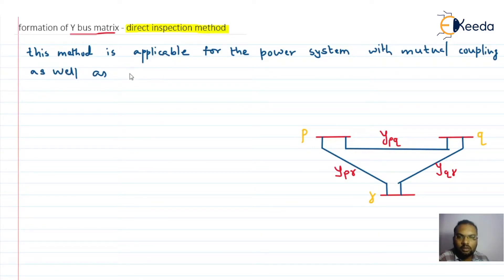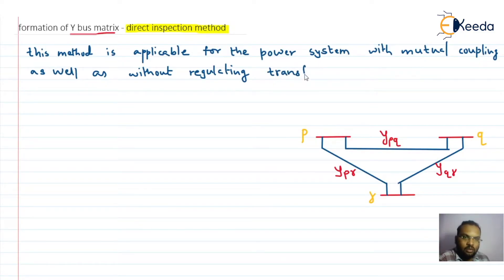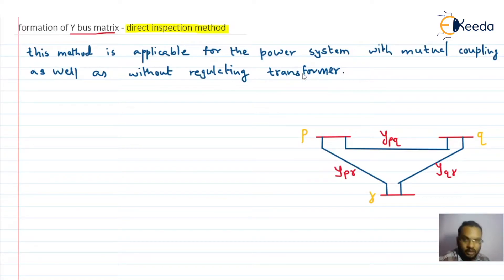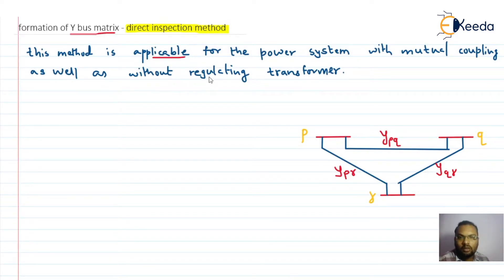The method is also applicable only in the absence of a regulating or phase-shifting transformer. If there is mutual coupling or a regulating transformer present in the power system, this method will not hold good. So it is applicable only when there is no mutual coupling and no regulating transformer.